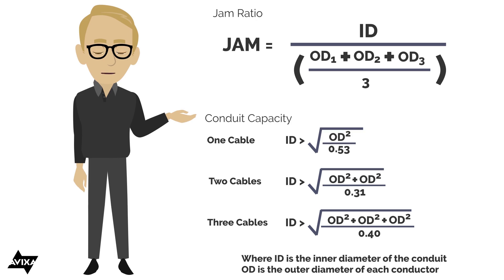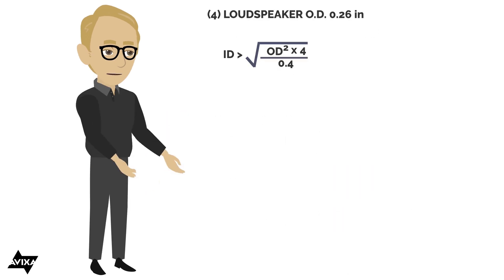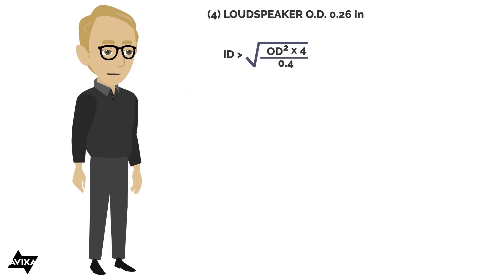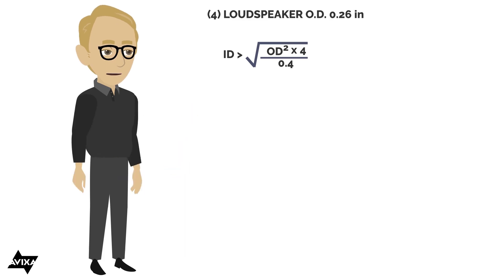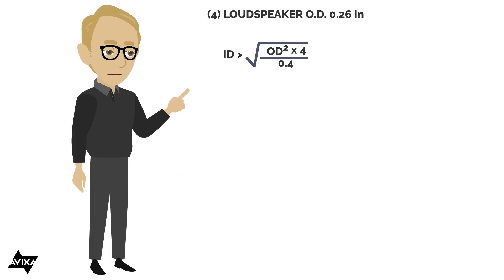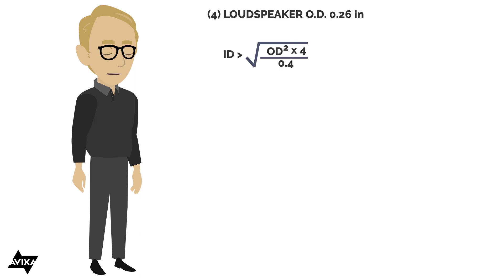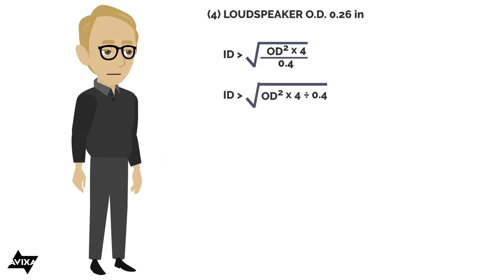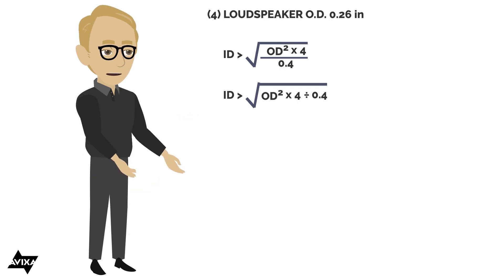Let's work through some examples. Let's say I'm going to pull four loudspeaker cables, and they each have an outer diameter of 0.26 inches. The formula tells me the inner diameter of the conduit I need must be greater than the square root of the outer diameter squared, times four — because I'm pulling four — divided by the fill percentage. Since I'm pulling three or more, I'm allowed the 40% fill.